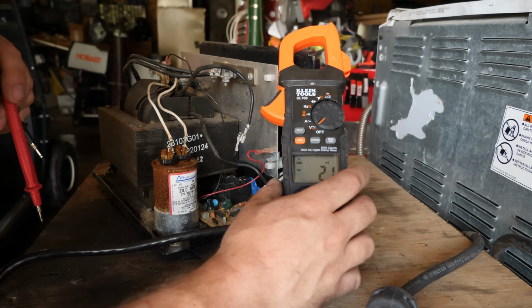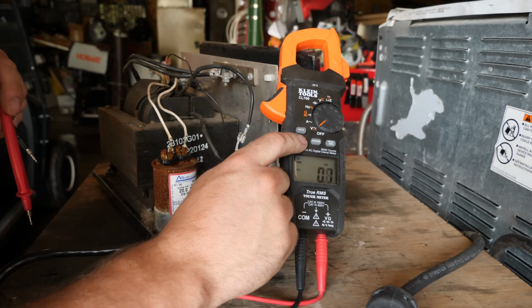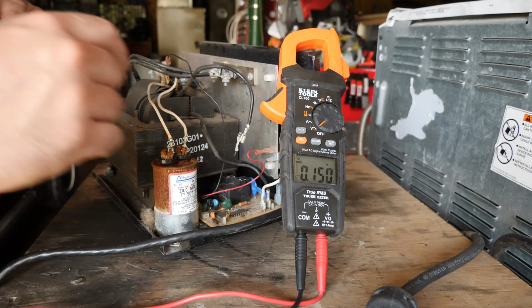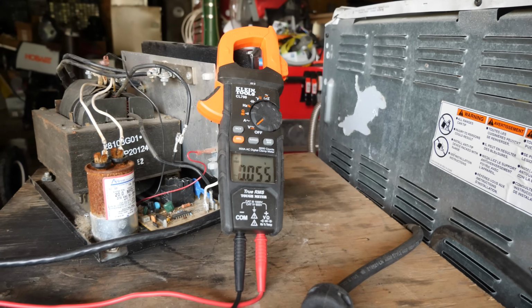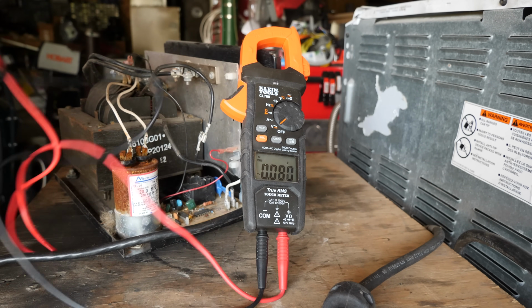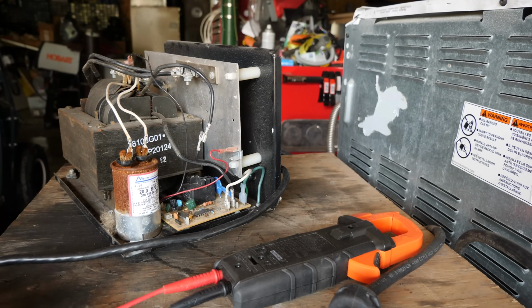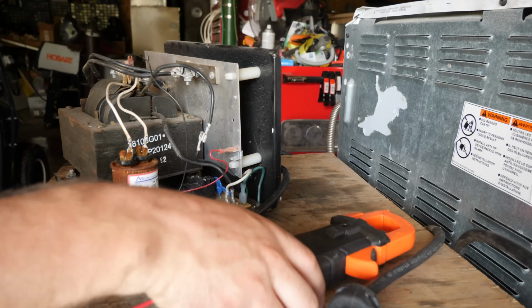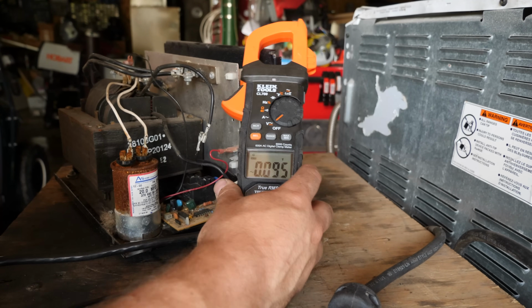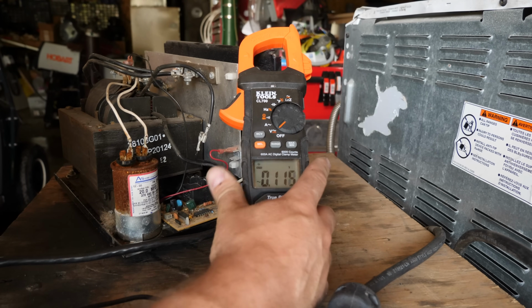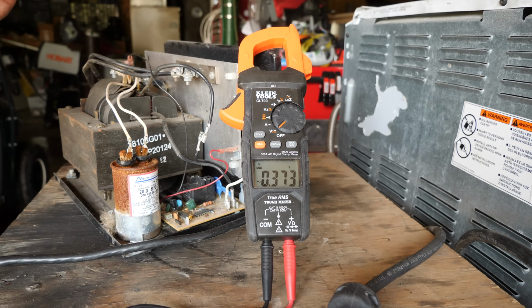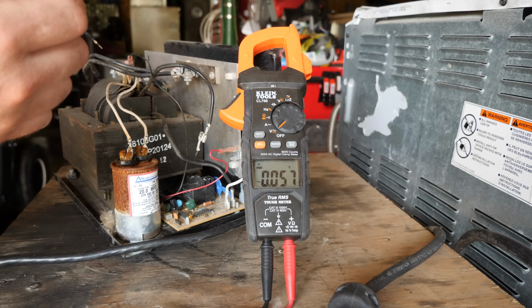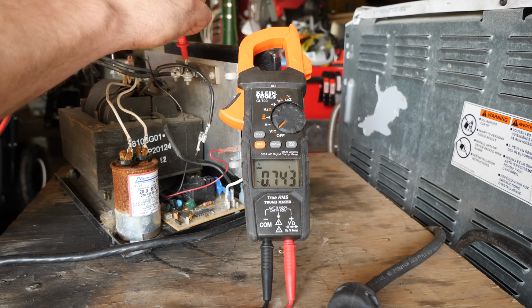What I'm going to do now is put this back on AC volts, and the reason is I'm going to test the output of the transformer. As soon as I untangle my meter leads here, we're going to check the output of the transformer before the split phase rectifier, or the half wave rectifier.